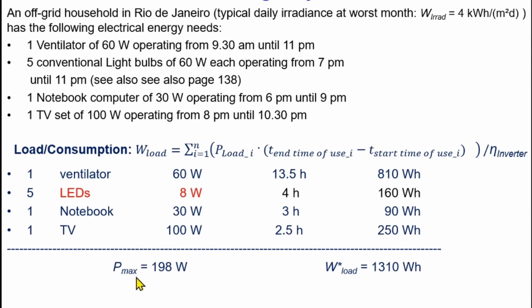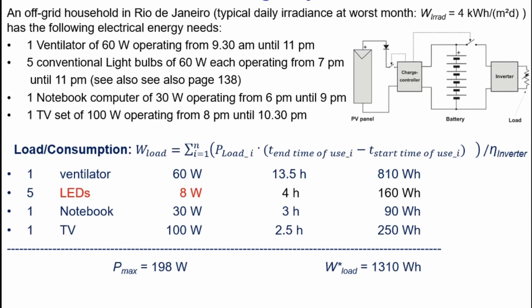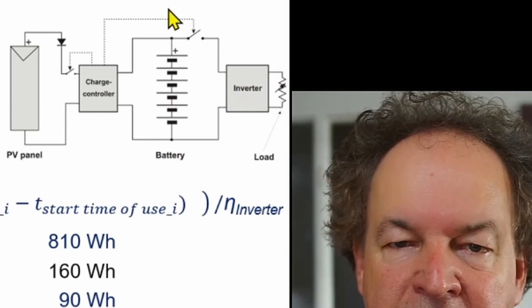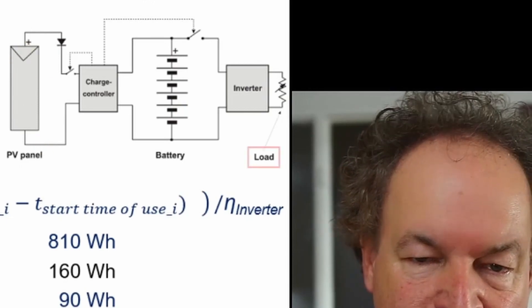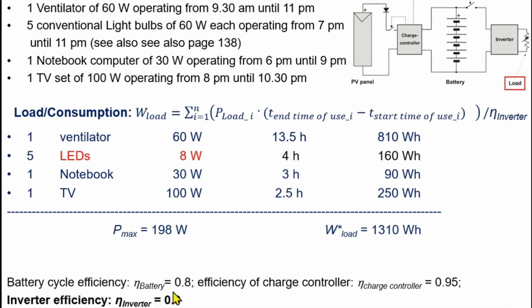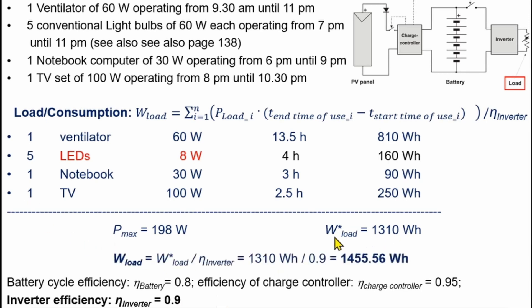For the inverter rating, if all appliances run simultaneously the maximum power is 198 watts, so an inverter of about 200 watts would suffice. Including the inverter efficiency of 0.9, we divide the load by the inverter efficiency. The actual load the PV system must supply is therefore 1,455.56 watt-hours per day.